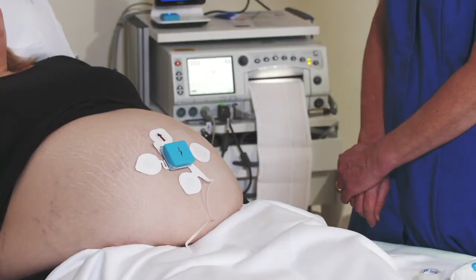If on the second attempt, you only manage to reduce the red cross to an orange O, it is always better to achieve a green tick. But if you only have one orange O, you can use the forward arrow button on the Novii screen to bypass the skin electrode check and commence monitoring. At the start, if you have a mixture of both red crosses and orange O's, always start with the red cross electrodes first. Just waiting a few minutes could be enough to take the orange O's to a green tick as the electrode gel is absorbed by the skin.